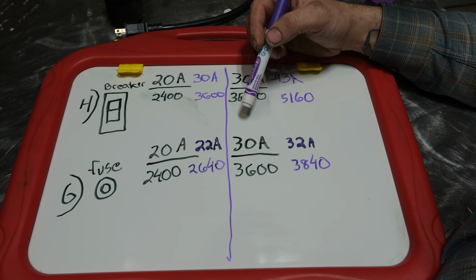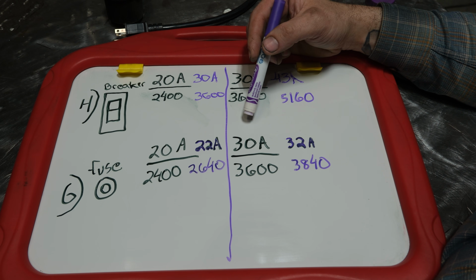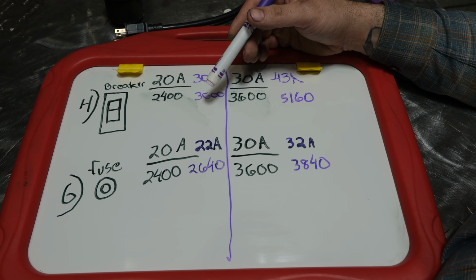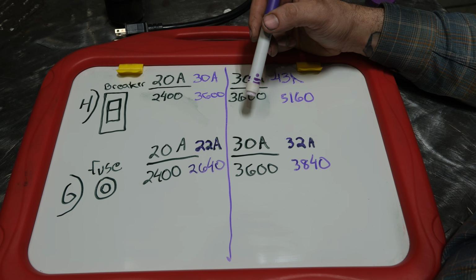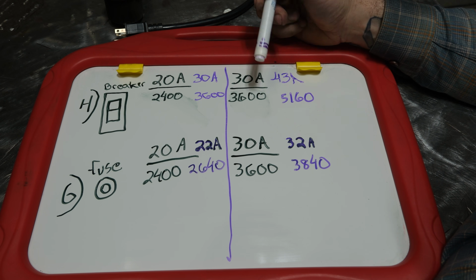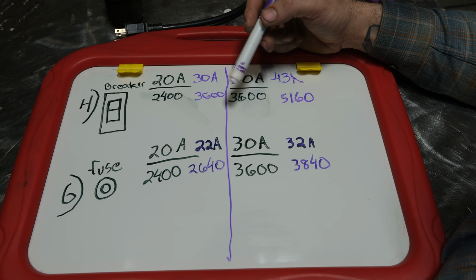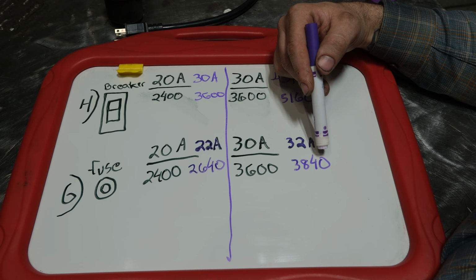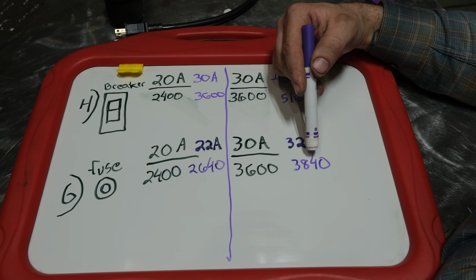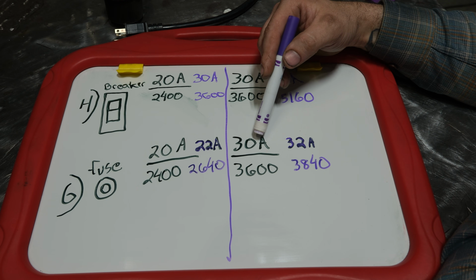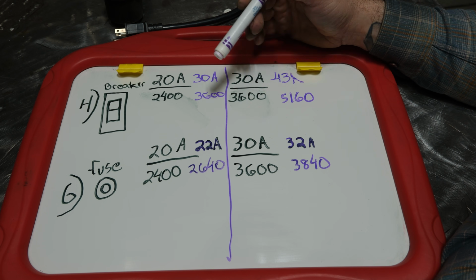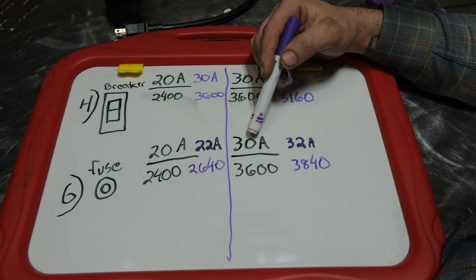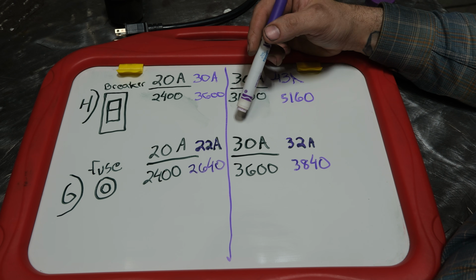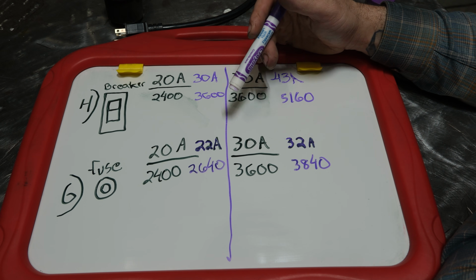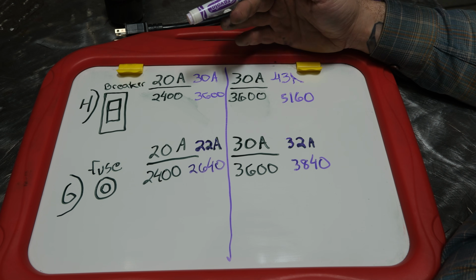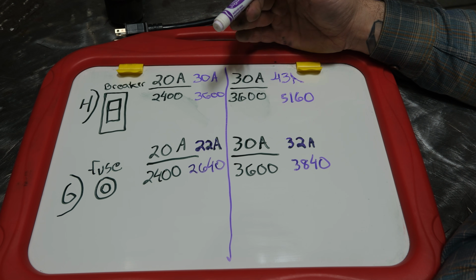The other problem is you're limited to how much generator output you have. In a household, you have a main breaker that's 20,000 plus watts of availability before that trips. Well, on a generator, whatever the generator's running watts are, that's all you have. So if you have a 3,550 running watt generator, guess what? You're not going to be able to even pull this even if you have a 30 amp breaker. And I've seen plenty of generators that have breakers that are rated for more than the output of the machine. And it's kind of all a marketing scam, to be honest. Like, oh, it's got a 30 amp. Yeah, it does, but you can only pull 28 amps through it.